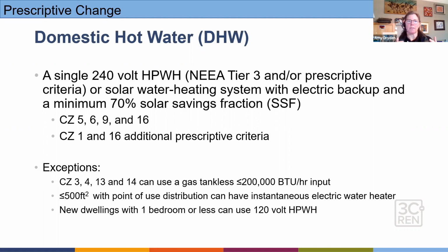So really we're driving toward the use of heat pump water heaters. And there are some exceptions, as you can see down below, creating some flexibility in different climate zones to use a gas tankless. And you can have a point of use, right? So if I have an instantaneous electric water heater at a point of use, like under a sink or in a master bathroom that may be farther away from my water heater, that's allowable. And the last bullet point there is that new dwelling units with 1 bedroom or less can use a 120 volt heat pump water heater. Those of you who have seen stuff coming out in the market, we are seeing these 120 volt, 15 amp, 20 amp heat pump water heaters that are compressor only, that are great for smaller units.